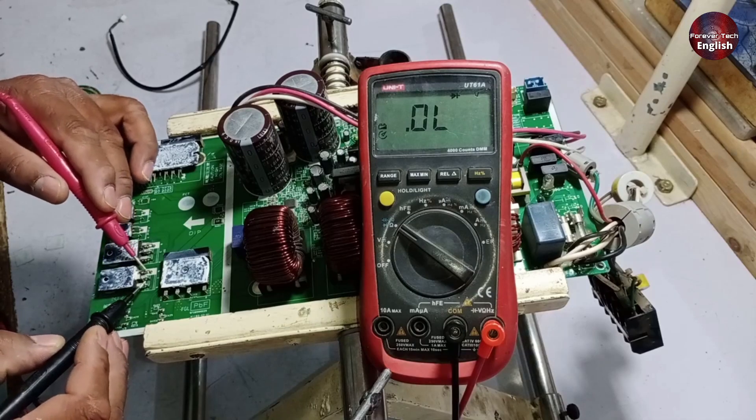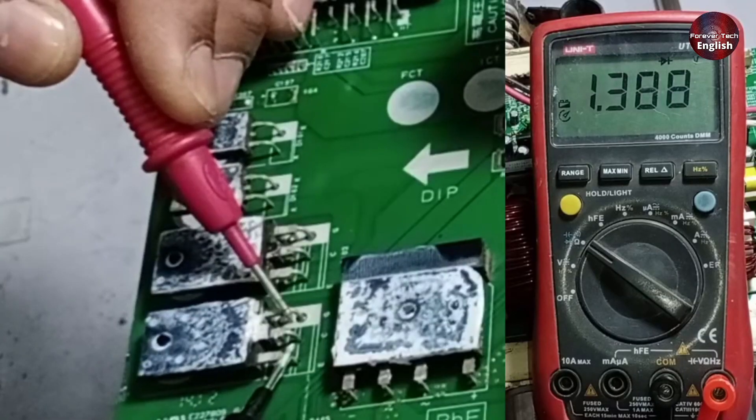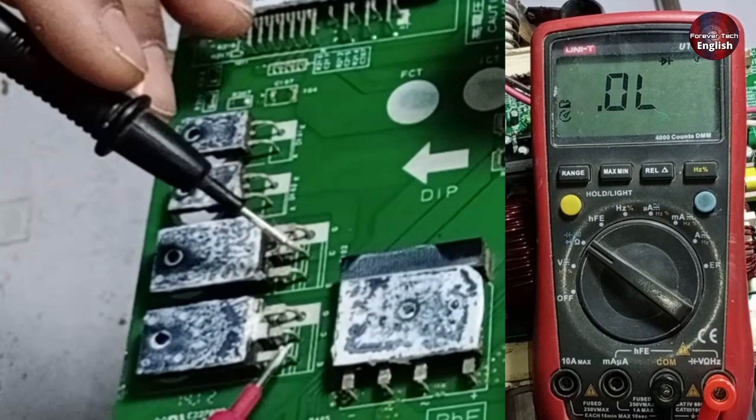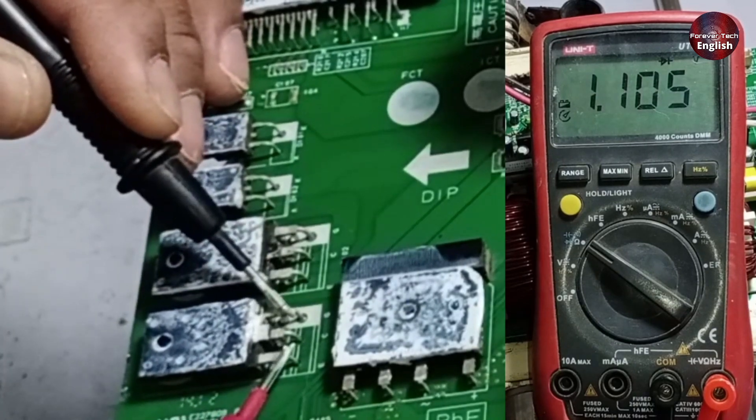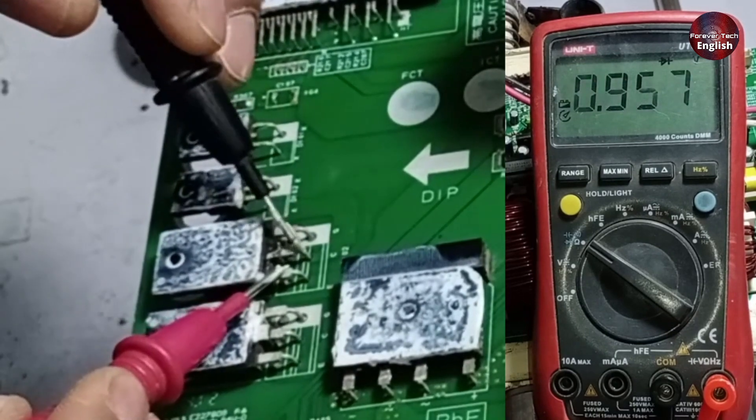Next, we will check the IGBTs. To check them, place the probes on any point. You should not see a reading of 0 anywhere, unless it is a common point. If it is common, that's fine, but if it's not common, there shouldn't be a reading of 0. There is nothing common here, so we keep checking, and there should be no issues. Everything here is fine.